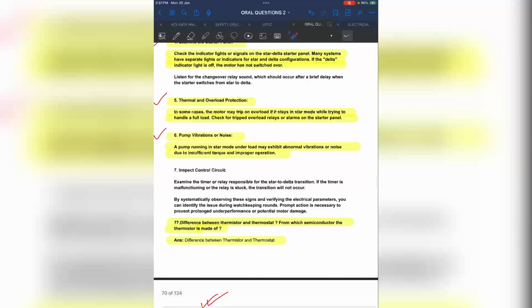And thermal overload protection. In some cases the motor may trip, because if the motor is running on a low voltage, the current will increase after a short time, and after that it will get overloaded. So from the overload protection you can check whether the circuit has tripped or not. Also the vibration and noise will increase, because the pump and motor are running on a low voltage. It means the motor is running on a low voltage, so there must be vibration or noise.